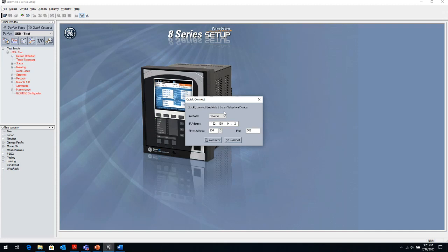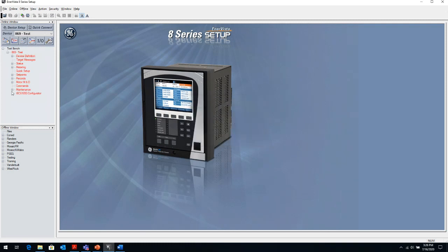So right now I'm connected through the Ethernet port. With the Ethernet port, you need to enter an IP address. There's also an option to have Wi-Fi. So if you do order a relay with Wi-Fi, you can connect via Wi-Fi. But note, you do need a hotspot for that. You need a hotspot for that relay to connect to, and then you connect to the hotspot to connect to the relay. So when we connect to the relay, this is on the left top. This is the menu that we're going to see.